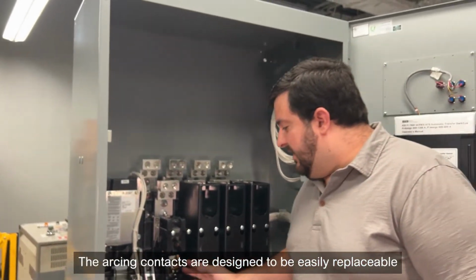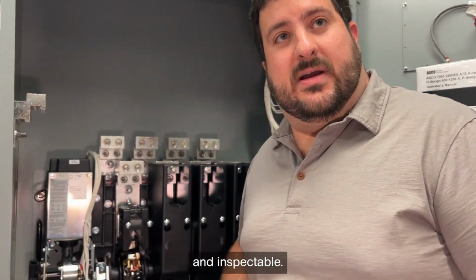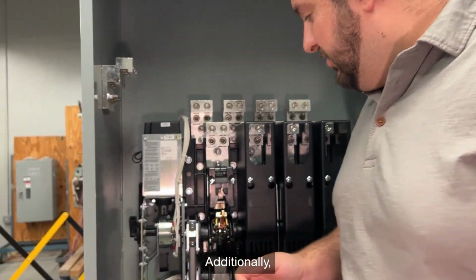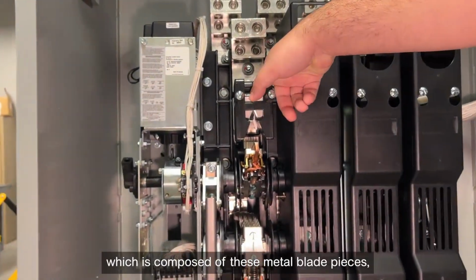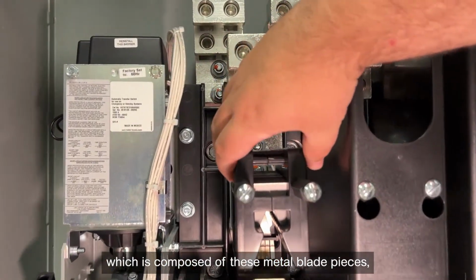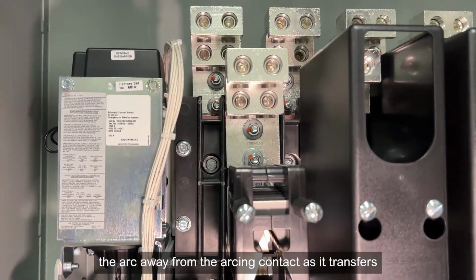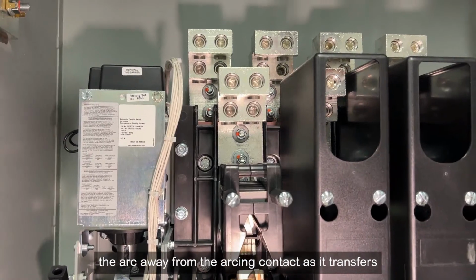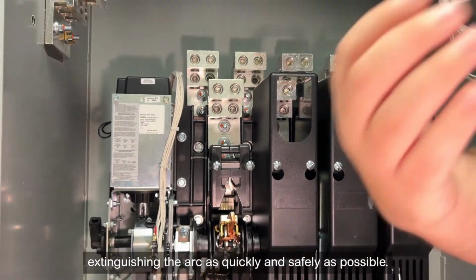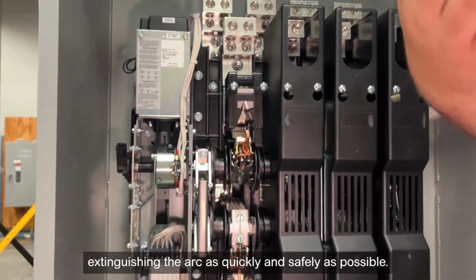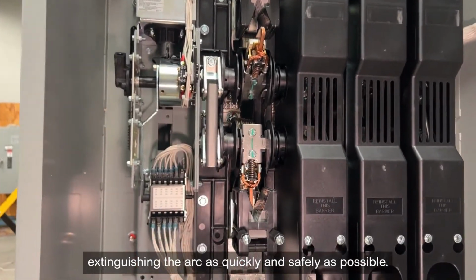The arcing contacts are designed to be easily replaceable and inspectable. Additionally, the arcing chute, which is composed of these metal blade pieces, is used to magnetically pull the arc away from the arcing contact as it transfers, extinguishing the arc as quickly and safely as possible.